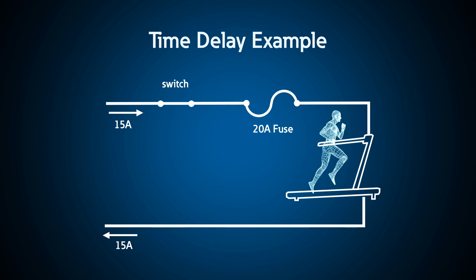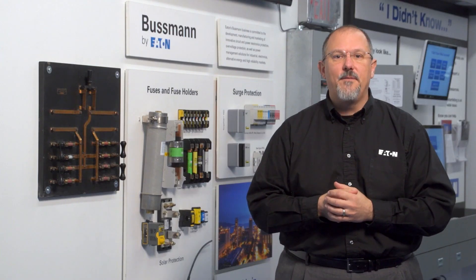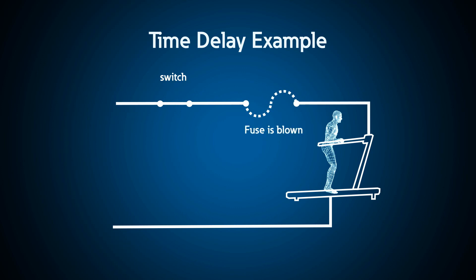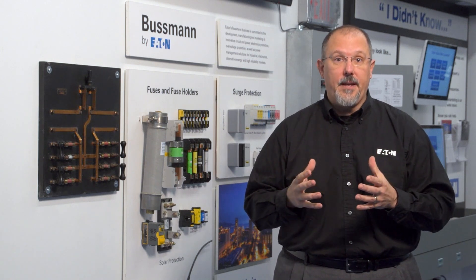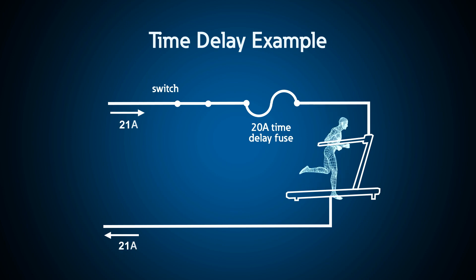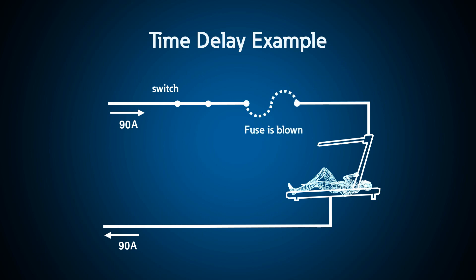For a treadmill with a motor running at 15 amps full load on a 20-amp circuit, the motor will pull roughly six times 15 amps for a short period on startup. A fast-acting fuse would open unnecessarily, so a time-delay fuse is needed — it lets the motor accelerate without opening. However, if the motor locks up, the fuse will only allow locked-rotor current to persist for so long before clearing the circuit.